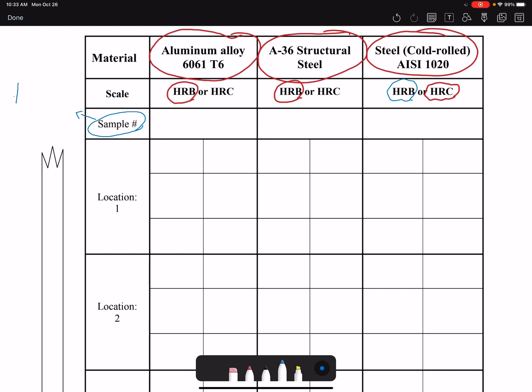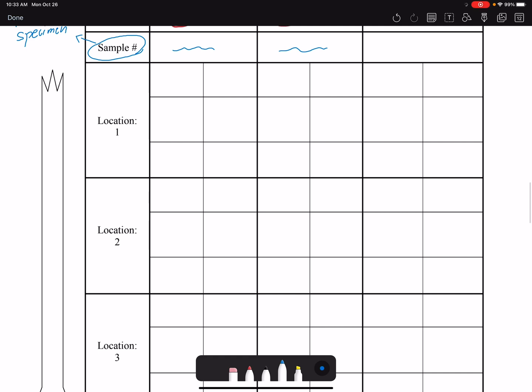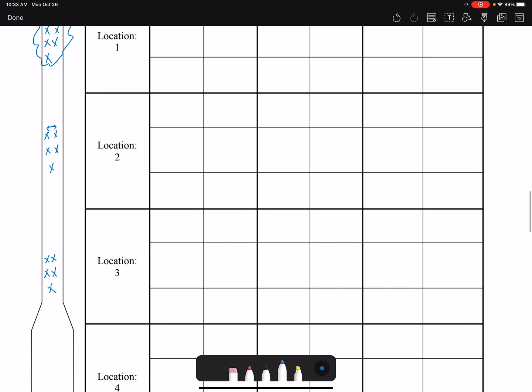We will use the tensile specimens broken in previous labs — Lab 1 and Lab 3. Record the specimen number, which provides information about strain rate and temperature used. We test four locations: Location 1 is close to the fracture area; Location 2 is further along the gauge; Location 3 and Location 4 are in the tab region. Perform multiple indentations per location and ensure they are not too close to each other to avoid influencing the results.